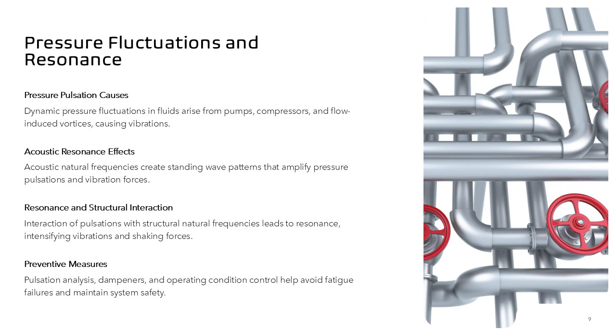Additionally, flow-induced excitation can occur when vortices form at deadleg branches or intrusive components, such as thermowells, producing periodic disturbances. These mechanisms often interact with structural natural frequencies, resulting in resonant conditions that amplify vibration. Preventive measures involve pulsation analysis during design, installation of pulsation dampeners, and careful control of operating conditions. Understanding pulsation dynamics is vital for avoiding fatigue failures and maintaining system integrity.